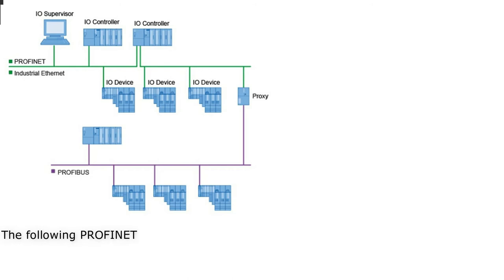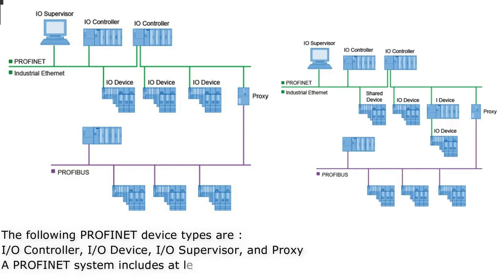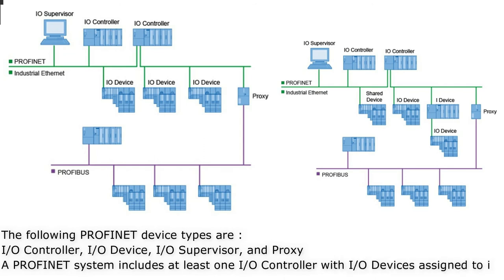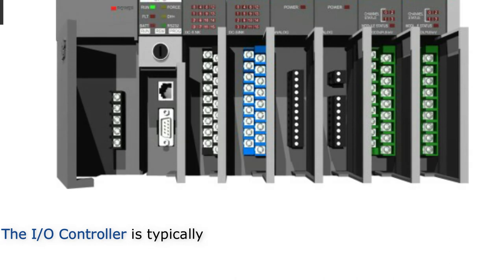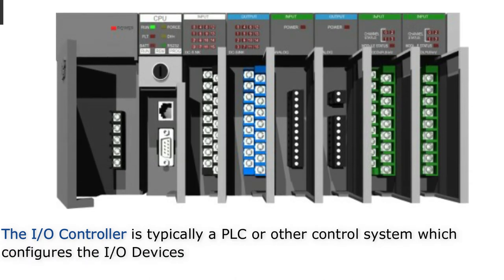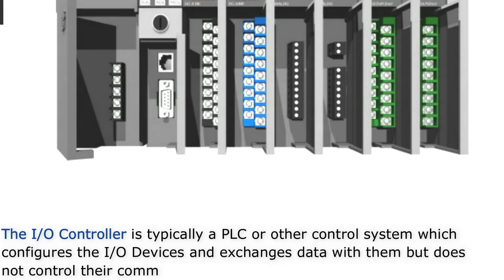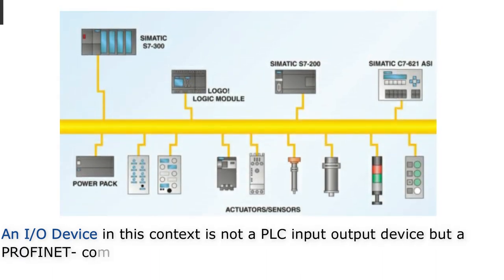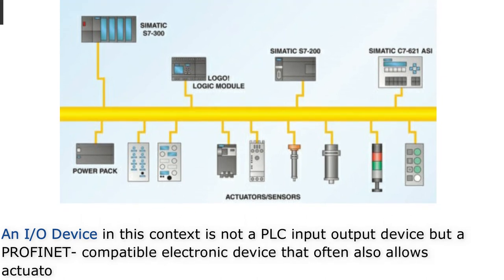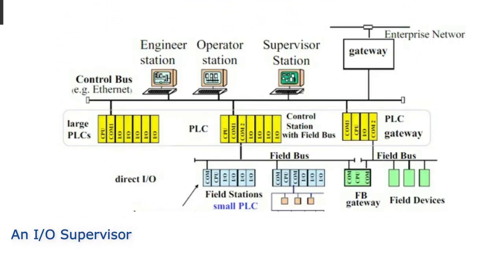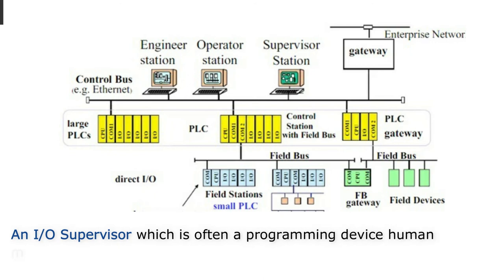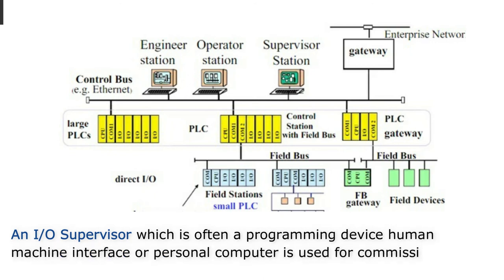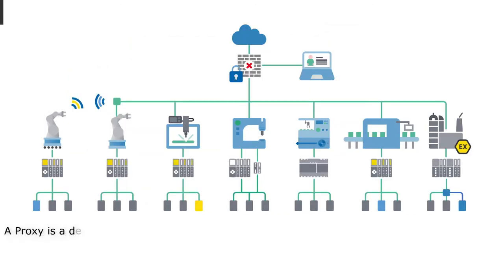The Profinet device types are: I-O controller, I-O device, I-O supervisor, and proxy. A Profinet system includes at least one I-O controller with I-O devices assigned to it. The I-O controller is typically a PLC or other control system that configures the I-O devices and exchanges data with them. An I-O device is a Profinet-compatible electronic device that often also allows actuators and sensors to be connected. An I-O supervisor, often a programming device, HMI, or PC, is used for commissioning, monitoring, and diagnostics. A proxy is a device that connects a Profinet network to a fieldbus such as Profibus.